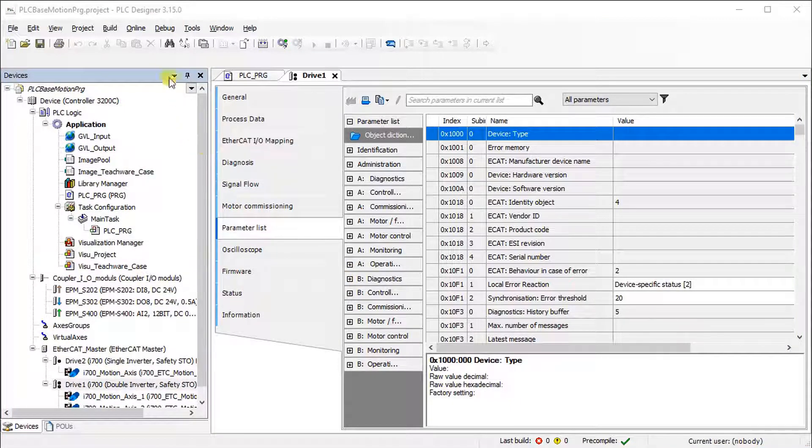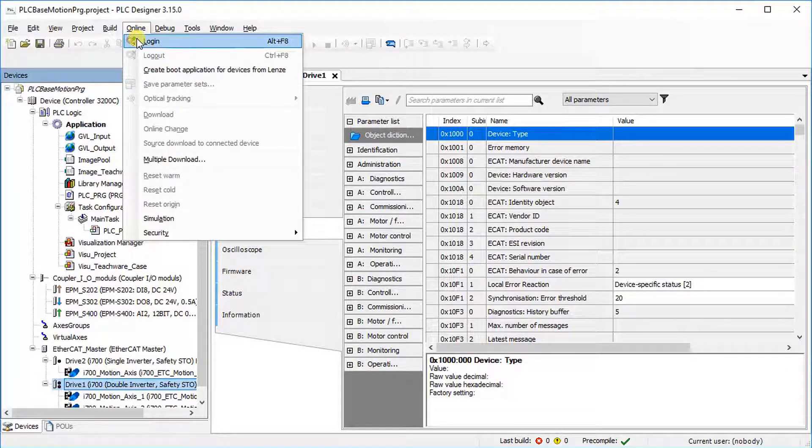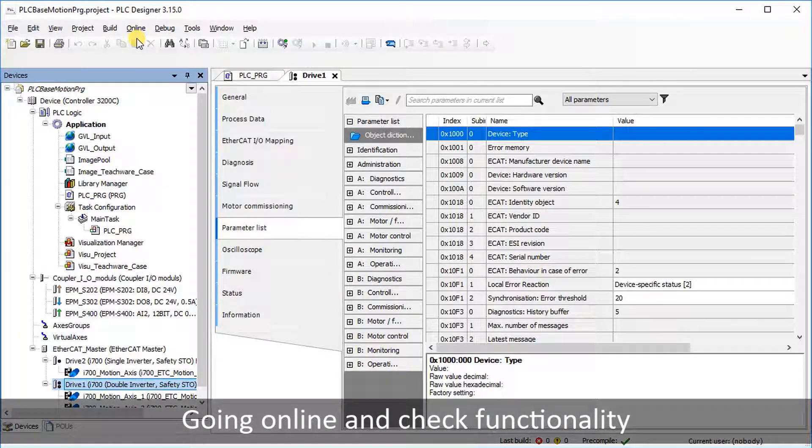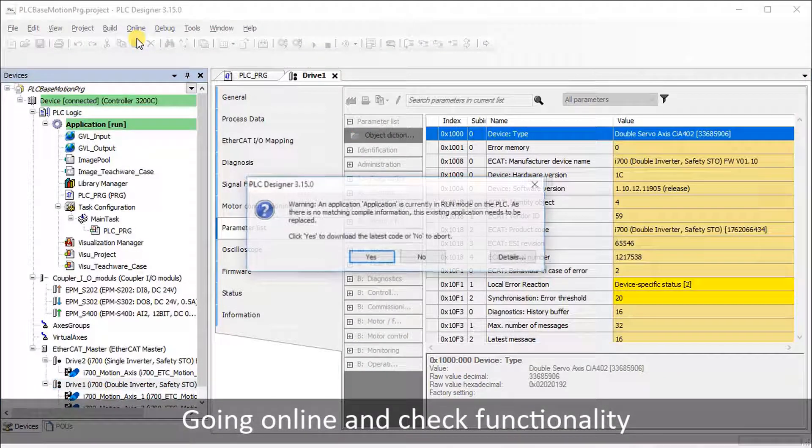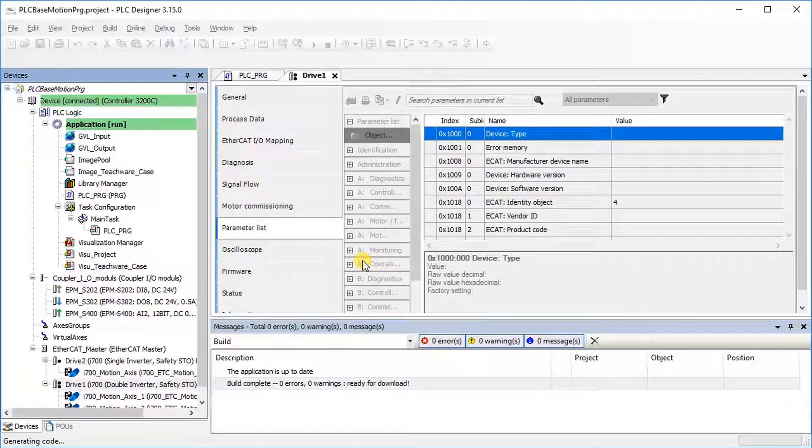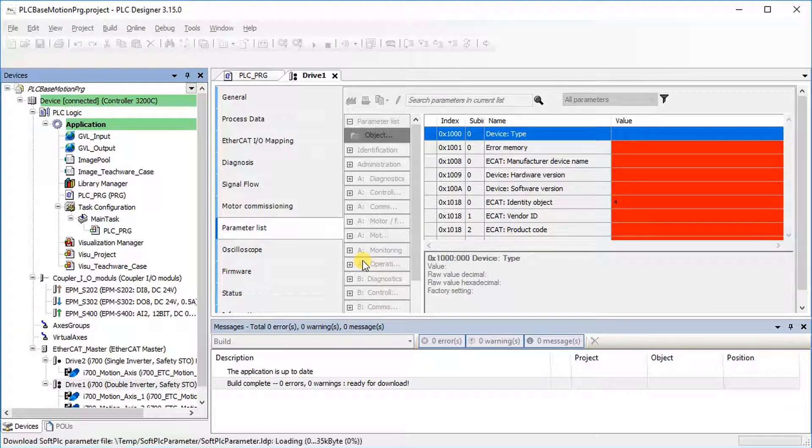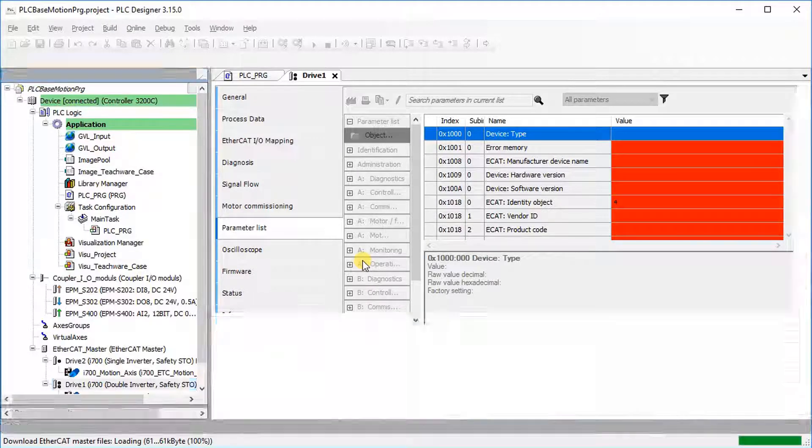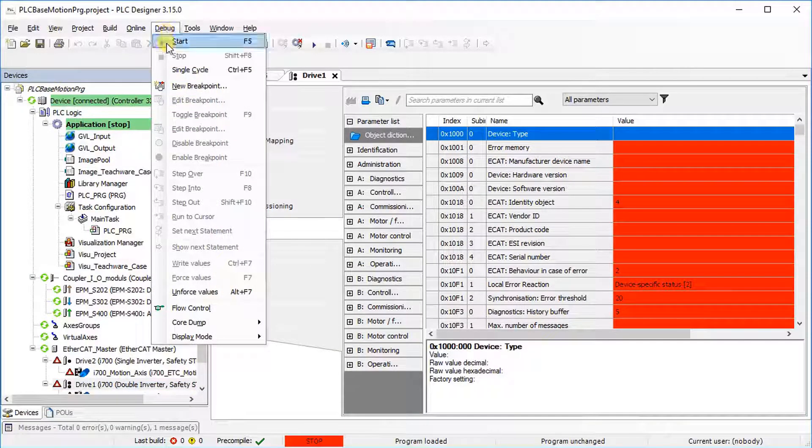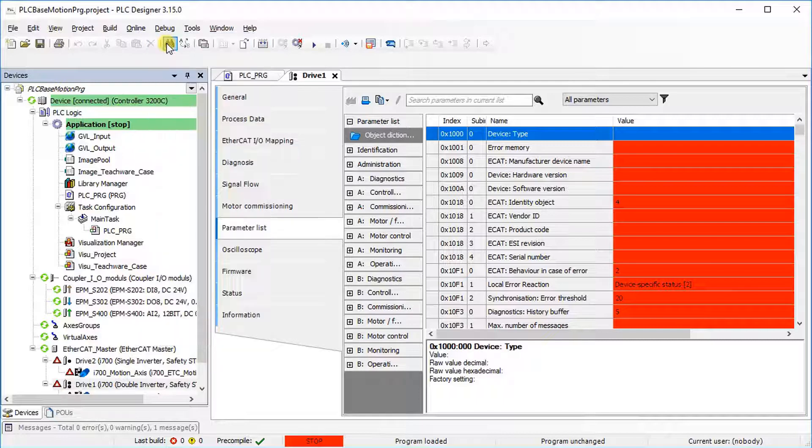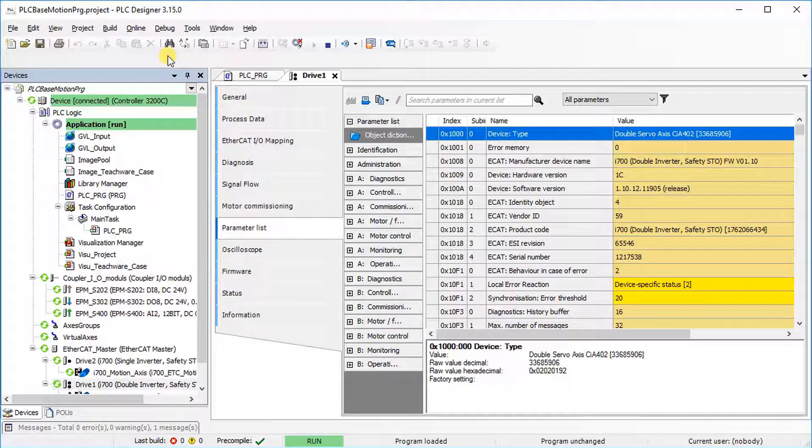Go to the Online tab and select Login, then confirm the warning message to download the project. Go to Debug tab and select Start to enable the controller. Select Save Parameter Sets under the Online tab to save the parameters in the drive.